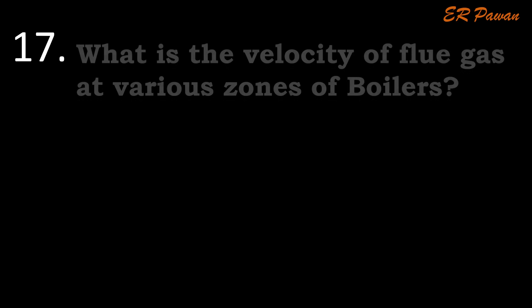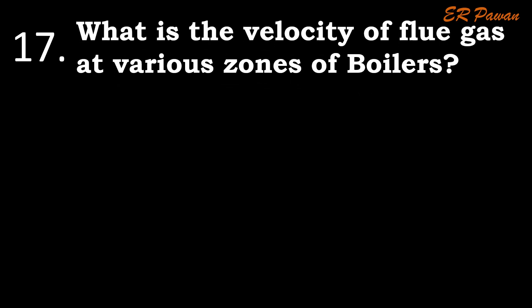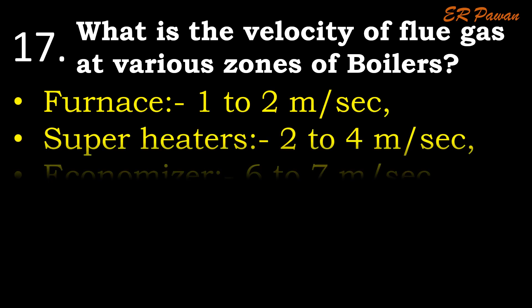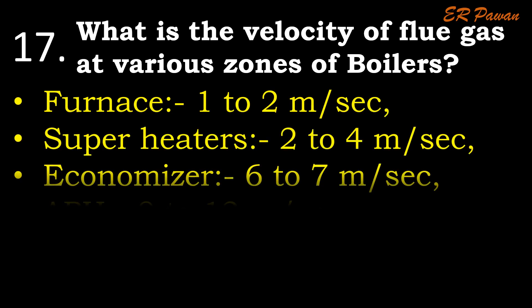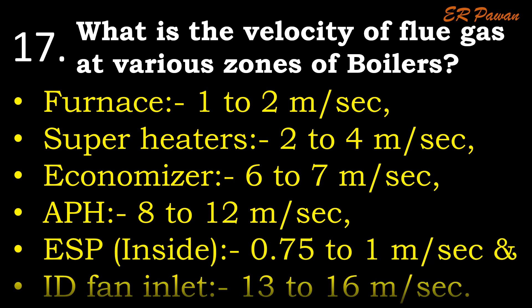Question 17: What is the velocity of flue gas at various zones of boilers? At furnace: 1 to 2 m/s. Super heaters: 2 to 4 m/s. Economizer: 6 to 7 m/s. APH: 8 to 12 m/s. ESP inside: 0.75 to 1 m/s. And at ID fan inlet: 13 to 16 m/s.